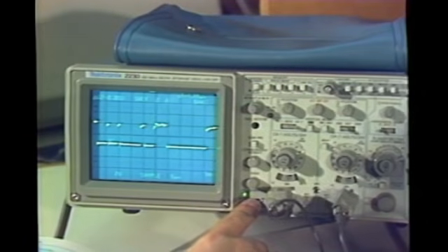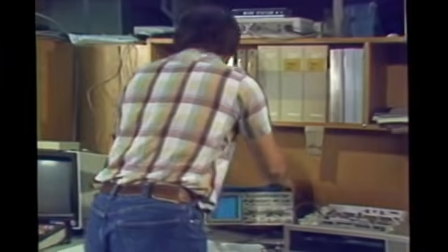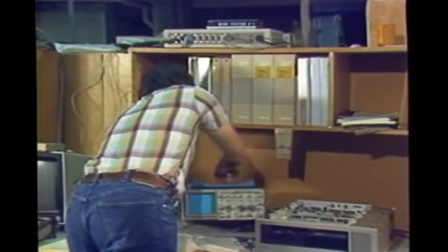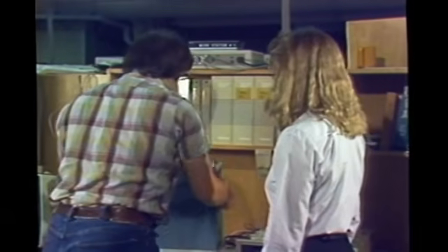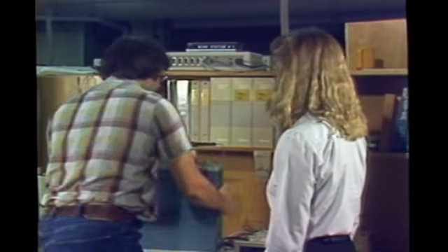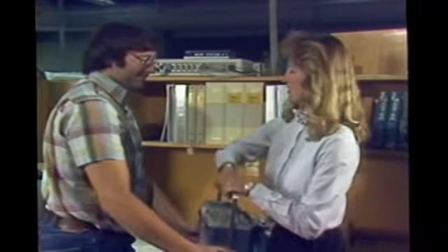An interesting use of this feature is to store waveforms at a remote location and return to a main location to compare the stored waveforms to a known reference. Or standard reference waveforms could be loaded into the scope and taken to the remote site for comparison.